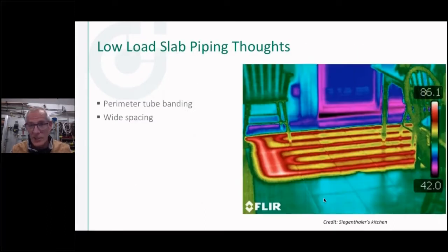So this is actually John Siegenthaler's kitchen, and he did this back, I think, in 1979. He understood this heat flux concept, and that was a low load room because he built a super insulated house. It looks like he's got a little air leakage around his doors. So what he did here, he said, what if I just loaded a band on the outer perimeter and don't put anything in the center of the room? Now my heat flux goes up, driving the output up to, instead of 10, 20, and my supply temperature to get that output is going to be 83 degrees. As you can see in the infrared picture right here, in some spots, right on top of the tube, he's probably about 85 degrees. 86 is the top end of the white. Down in here, he's probably in the mid 80 degree temperature across that.